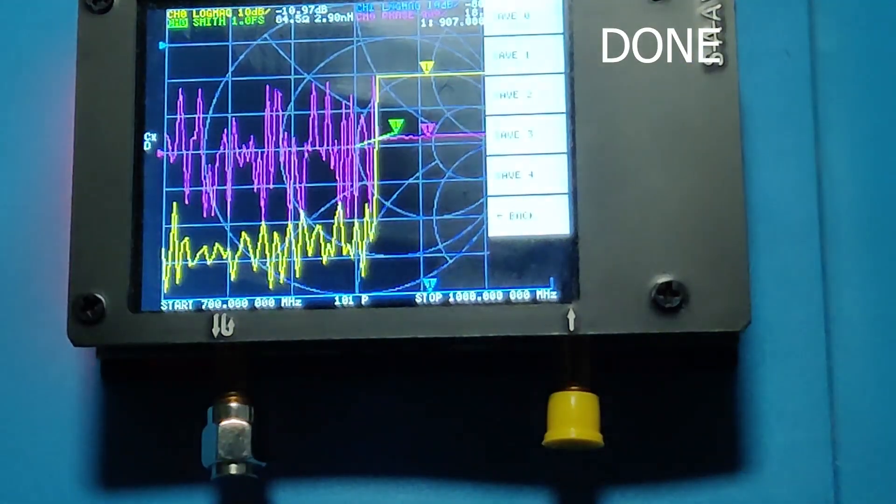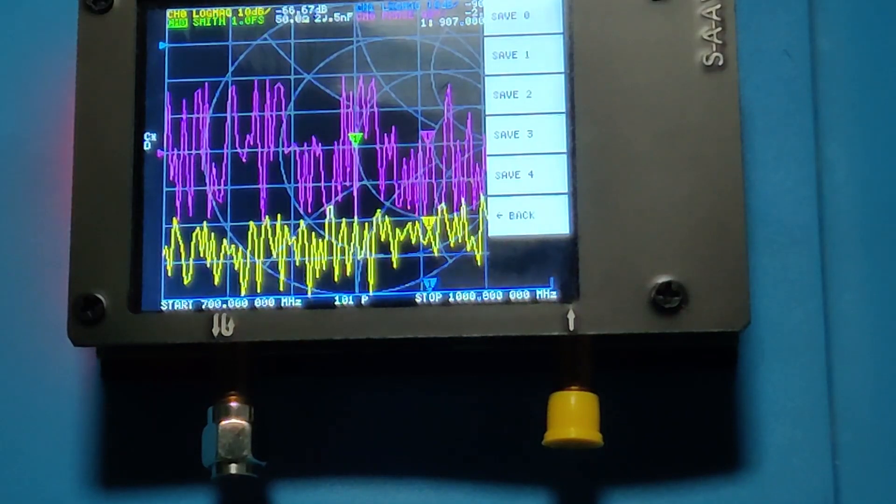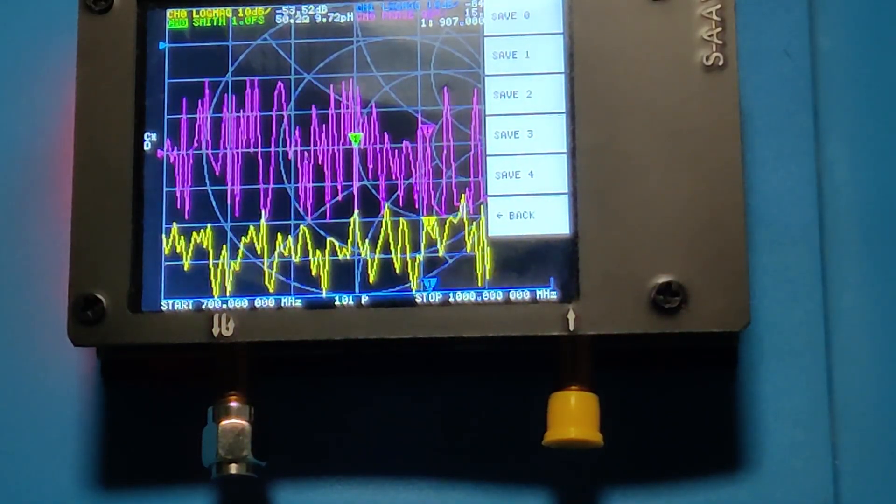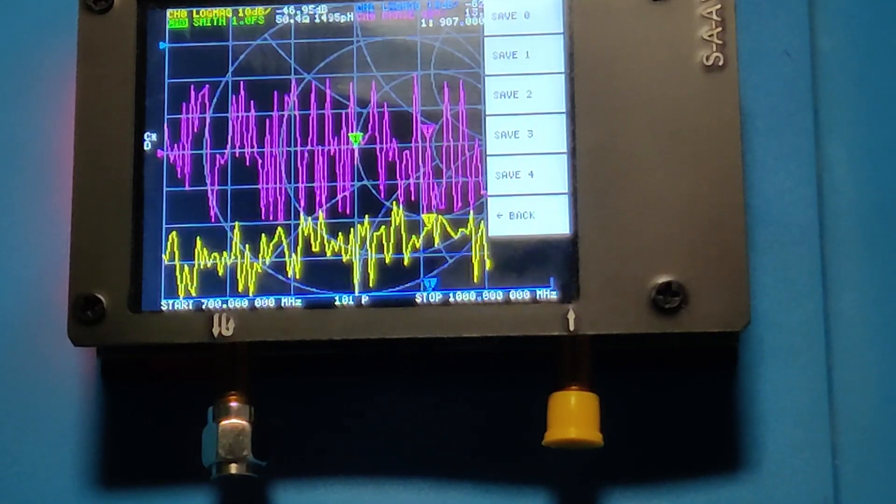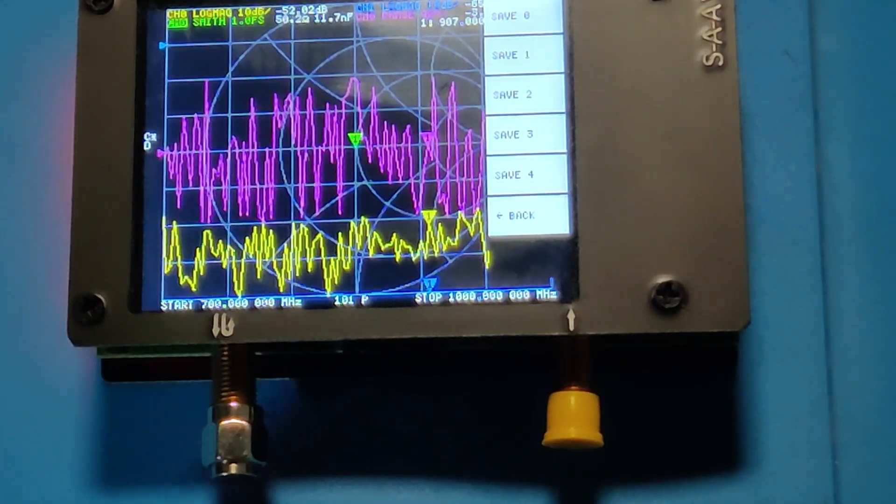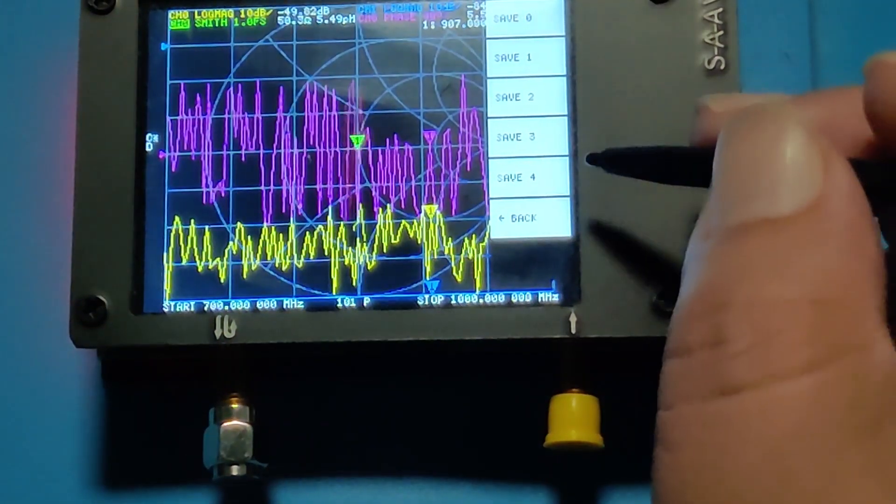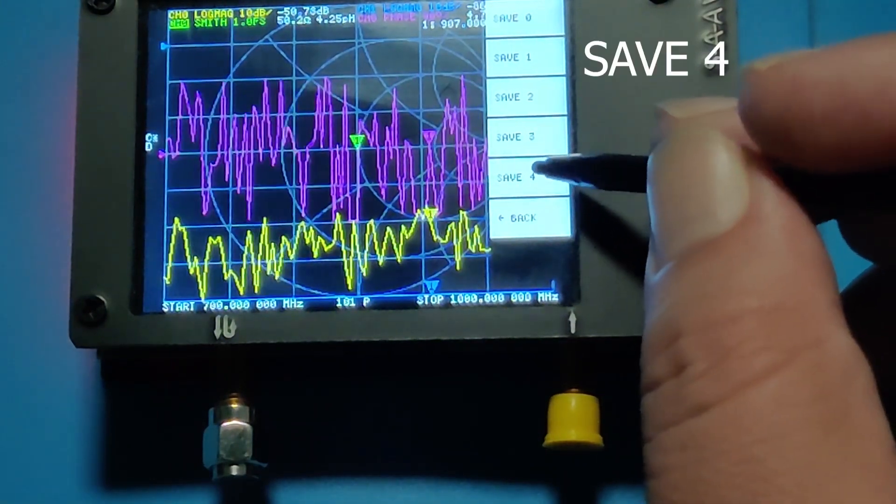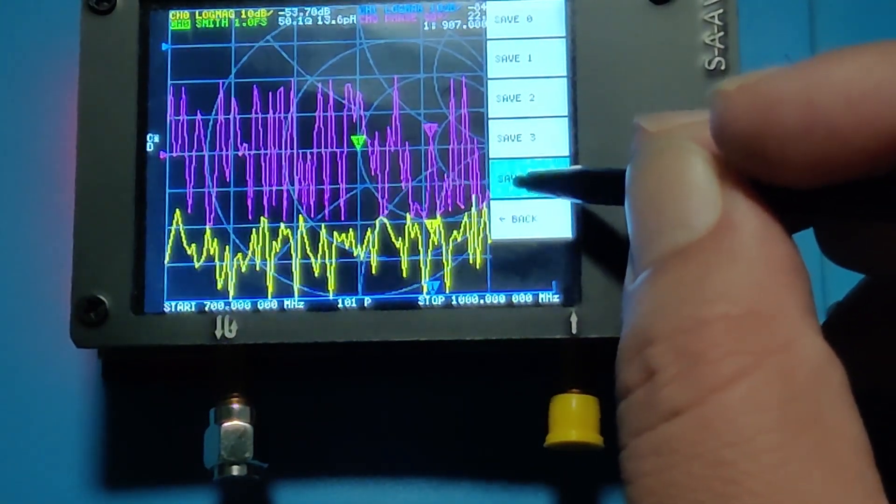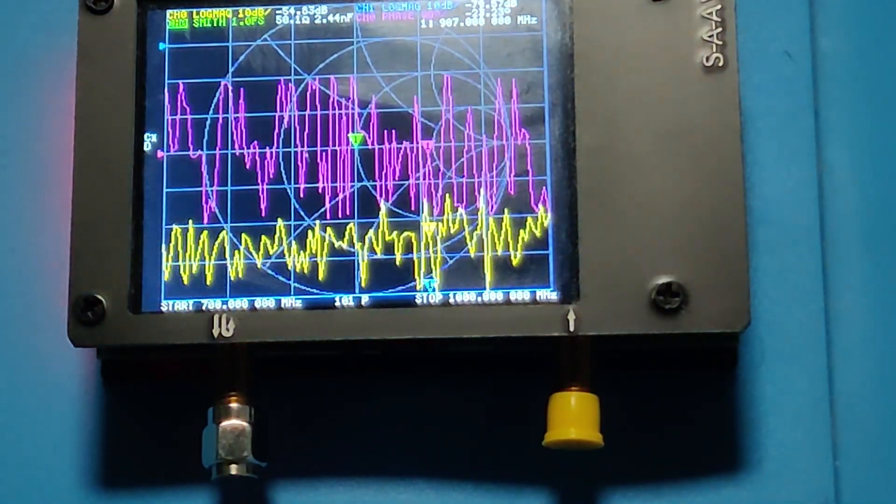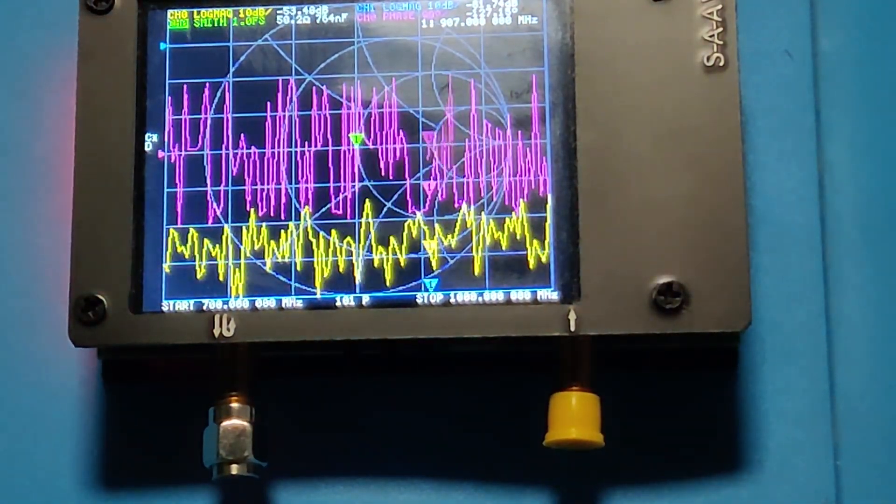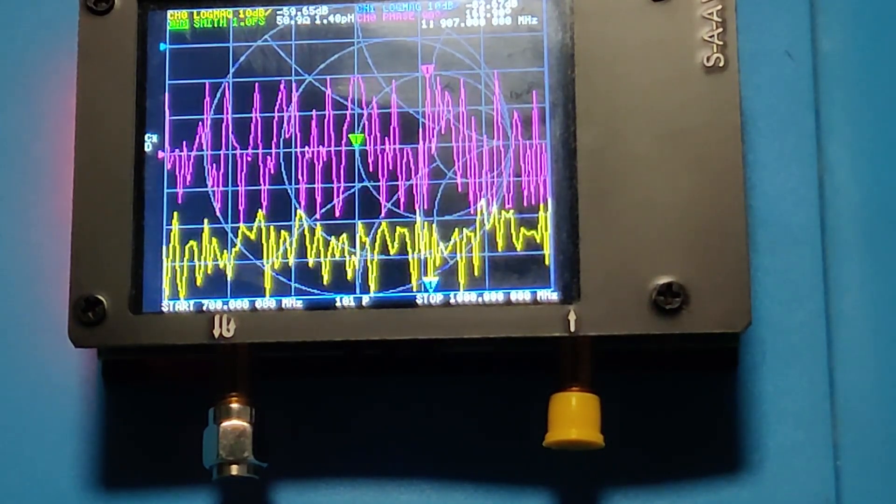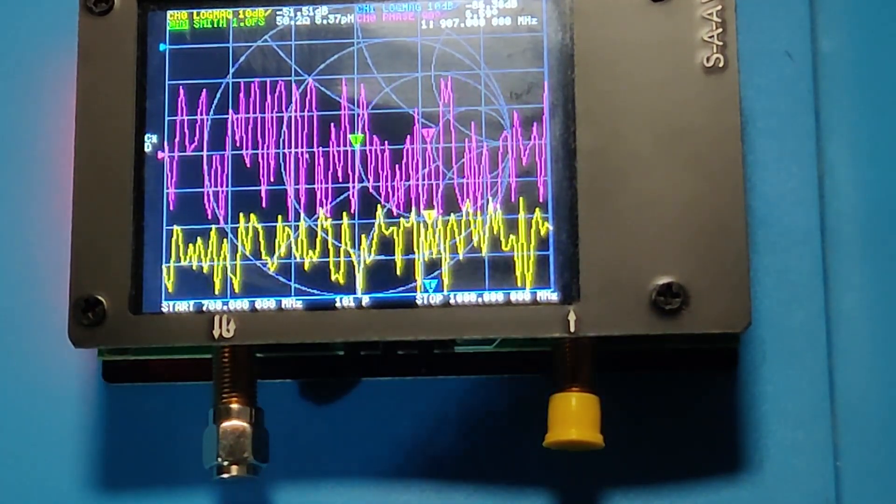Now it is giving us options to save this calibration. We see five memory locations. Pick anyone you like, but remember any previous calibration in that location will be wiped out. I select save 4. This calibration has been saved in the save 4 memory location. We can recall it whenever we need it. After saving, we are done with the calibration.